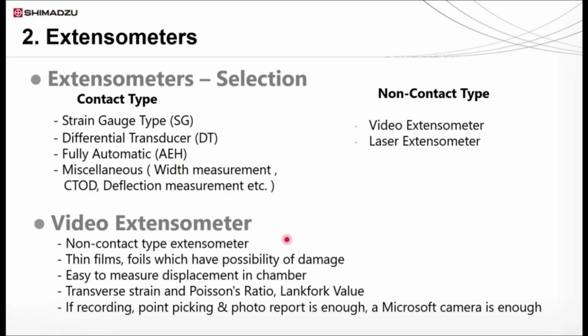Let me give you a brief idea about video extensometer. Video extensometers are non-contact type extensometers. A video extensometer is especially useful when the sample is thin film or foil which has the possibility of damage when a contact type is clipped. Video extensometer is also useful for measuring the displacement inside the chamber. Video extensometer has an advantage when the customer wants to measure the transverse strain together with the longitudinal strain, or measurements like Poisson's ratio, Lankford value, etc.